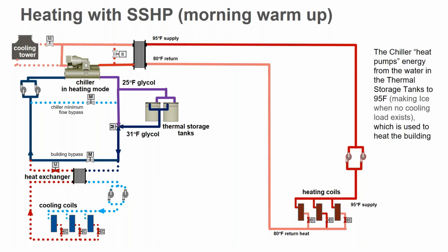If you were heating with a storage source heat pump in the morning, well, you really just have a chiller making ice as you would in the summertime, but that condenser energy is not going to the cooling tower, which is where you'd be throwing it out of the building. That energy is going, we'll call it here now, to a plate and frame, and that energy is going to heating the perimeter or whatever heating zones that you have.